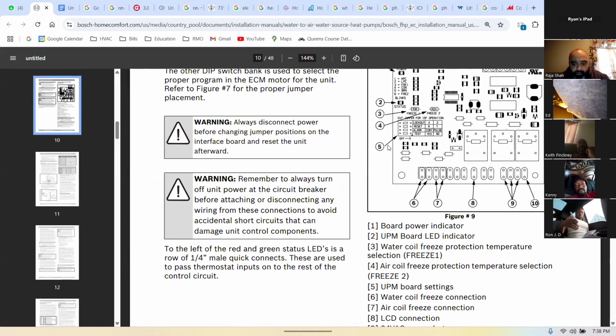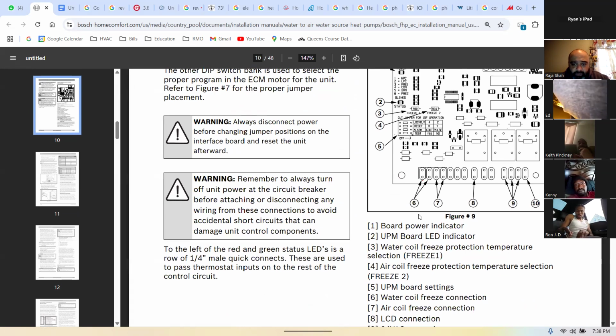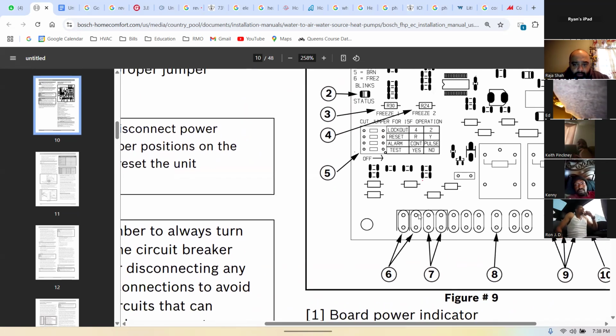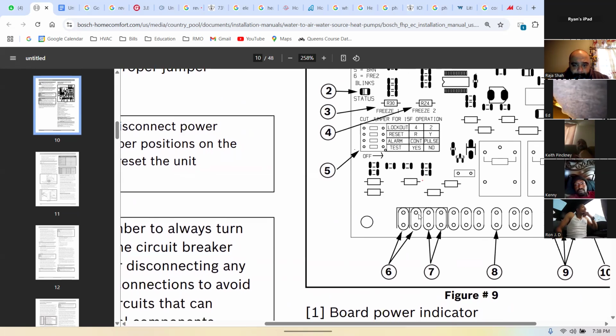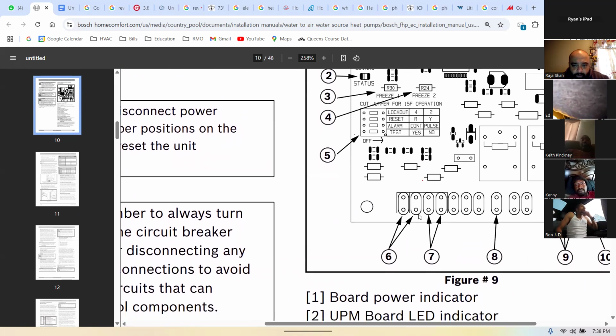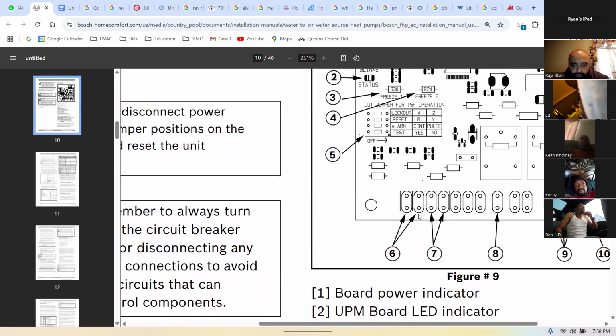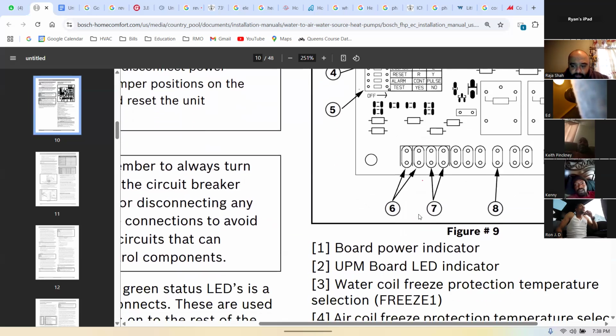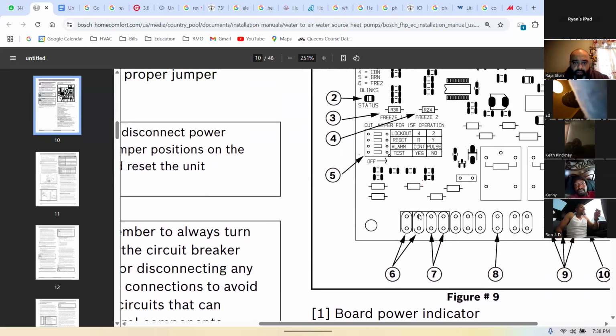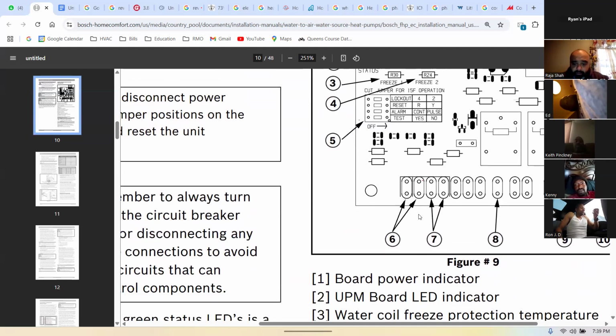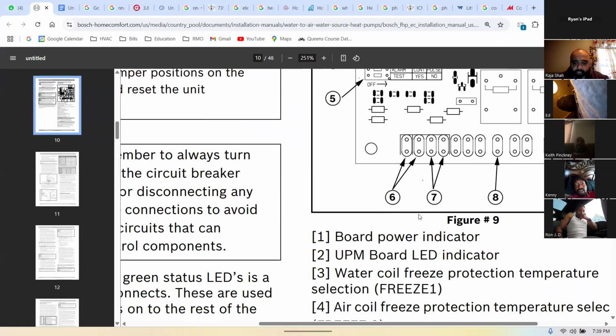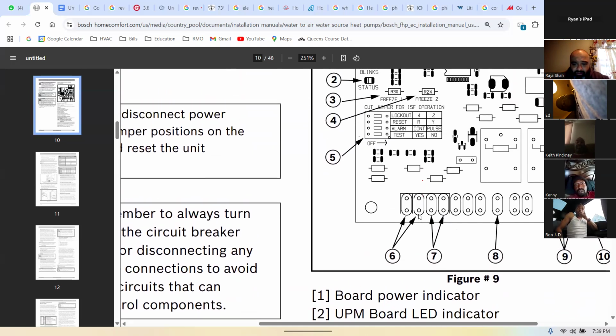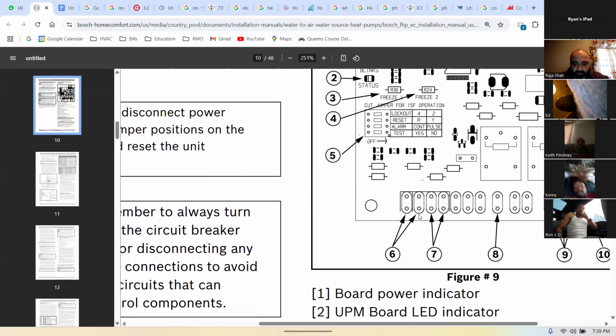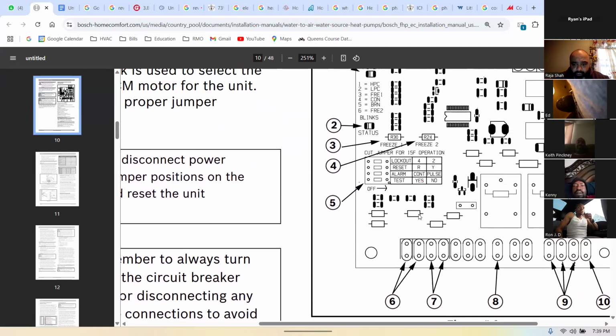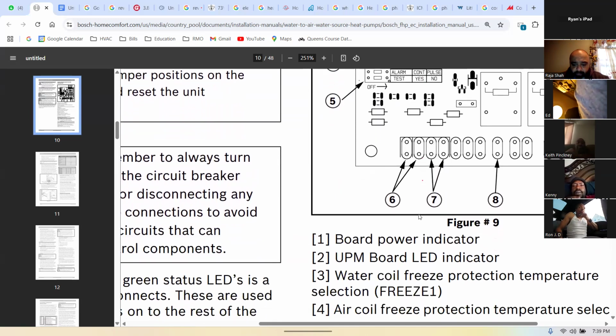Now number 3, it's saying the water coil freeze protection temperature selection. R30, R24. So what do you do with that? It's for freeze stat 1 and 2, right? No, but you see where it says 3, water coil? It lets you pick the temperature. It might be a dip switch or something over there, right?